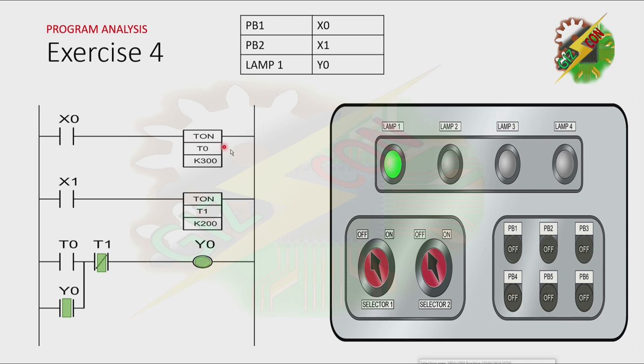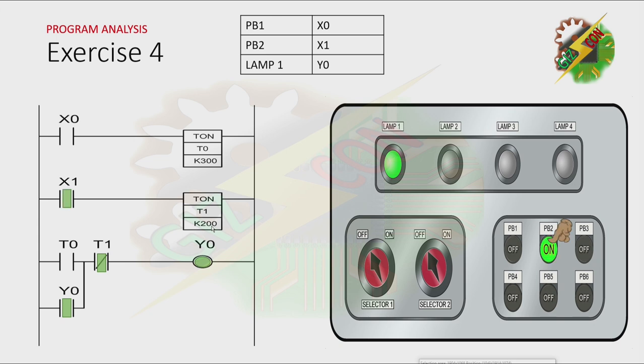Even if we release X0 and T0 is not activated anymore, the lamp is still on because there is a latching here. The only way to turn it off is by activating T1. To activate T1, we need to energize X1. When we energize X1, T1 will be activated after 2 seconds. Let's press PB2 to energize X1 — timer 1 will be activated after 2 seconds.